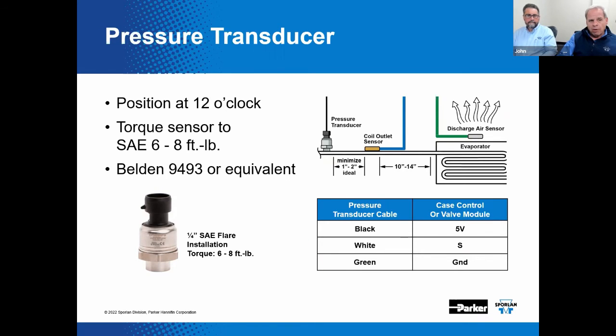What would be important also with this, John, as far as spacing is concerned? Well, you really kind of want to minimize that distance between the coil outlet sensor and the pressure transducer. You're using those two inputs to measure your superheat, and so the closer to the same position you're taking that, the better reading you're going to get on that. So here, pressure transducer and the temperature sensor, no more than an inch or two as ideal as that diagram shows, and then you want the coil outlet sensor at about roughly 12 inches give or take from the actual last two passes of the coil. Makes sense to me.